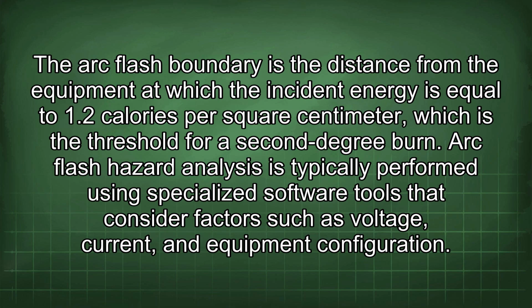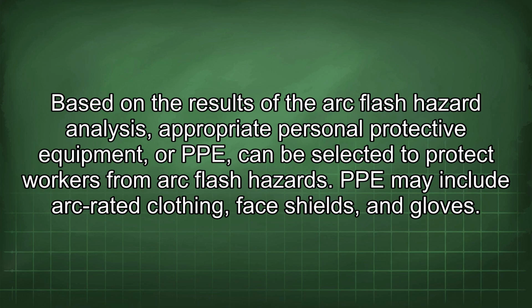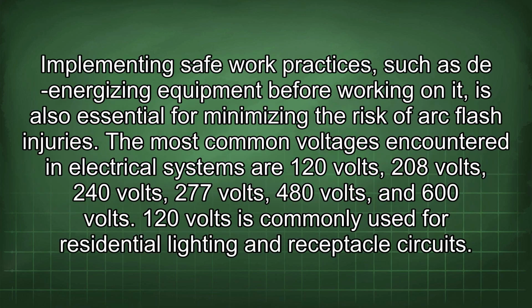Arc flash hazard analysis is typically performed using specialized software tools that consider factors such as voltage, current, and equipment configuration. Based on the results of the arc flash hazard analysis, appropriate personal protective equipment, or PPE, can be selected to protect workers from arc flash hazard. PPE may include arc-rated clothing, face shields, and gloves.